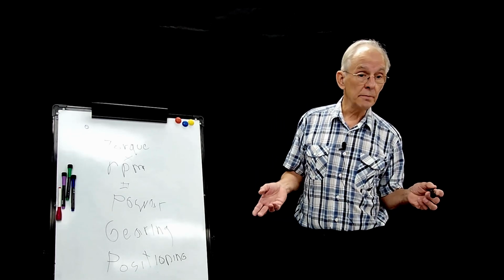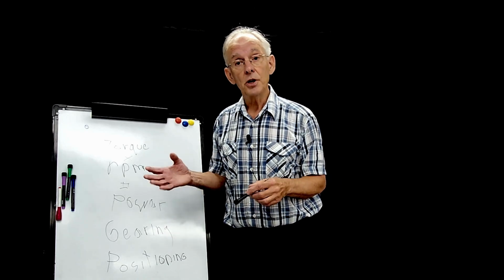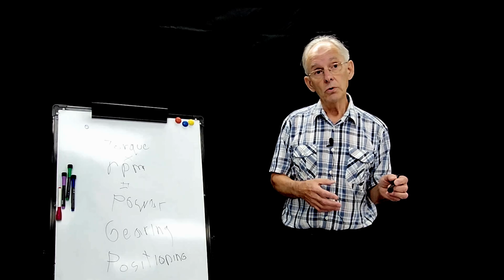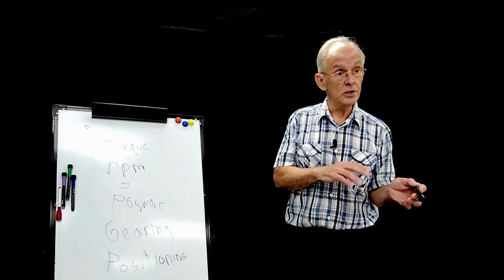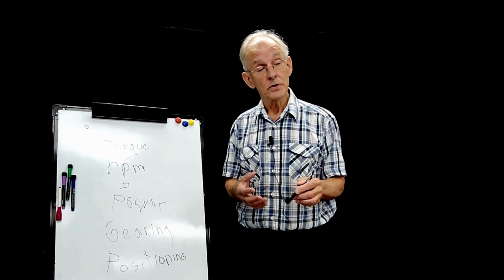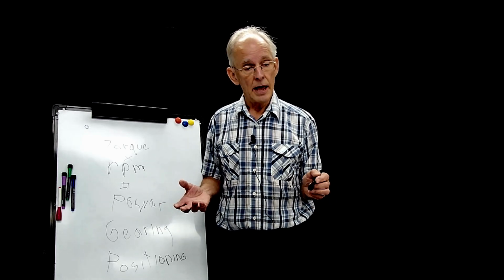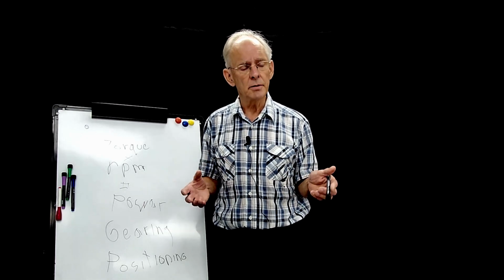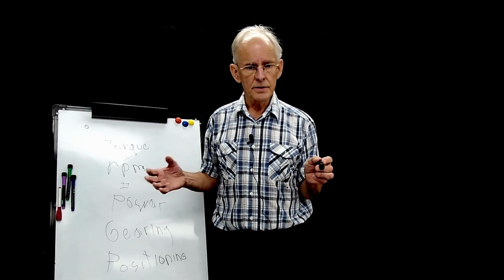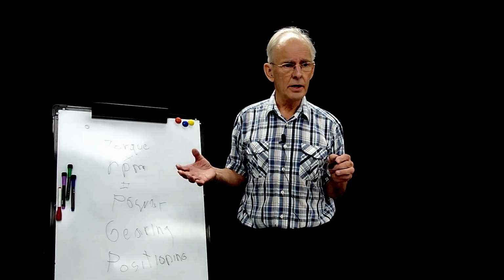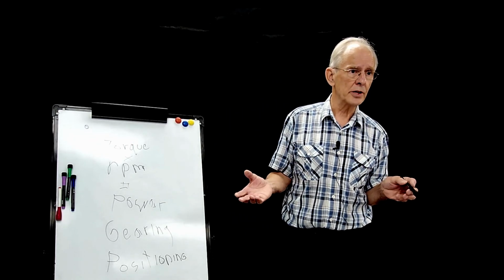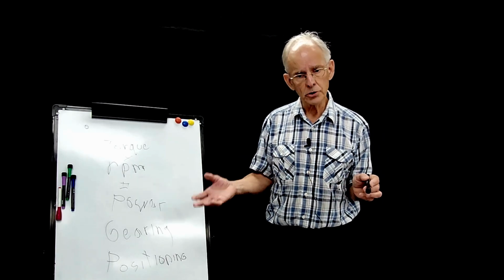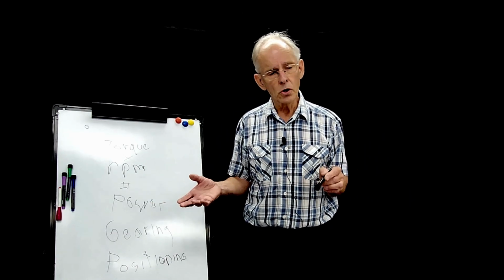Now, servos can be both AC and DC, because as long as you have the encoder, you really don't care what the power source is. So there are brushed DC servos and there are AC servos that don't have any brushes. But from the point of view of selecting the motor, they work the same way. And the primary differences in brushed versus brushless is cost. The brush motors are cheaper and the brushless motor is more expensive, and also the lifespan.